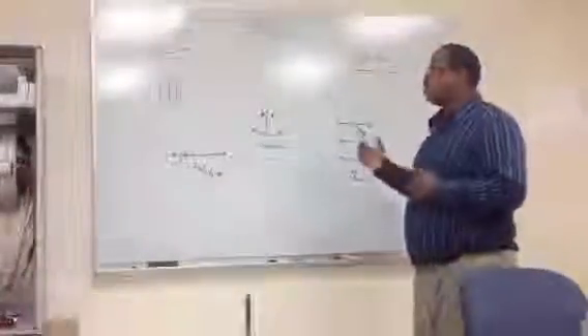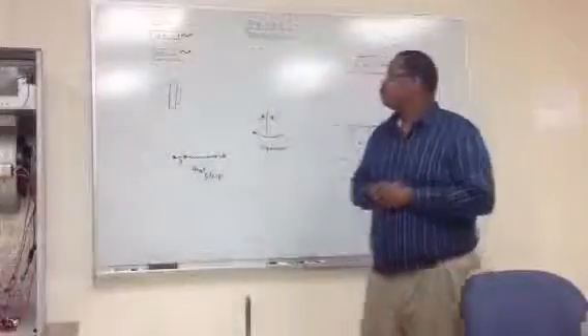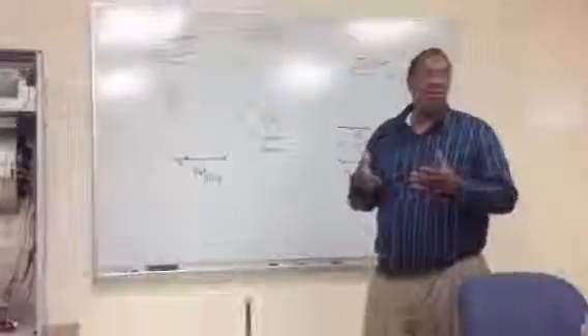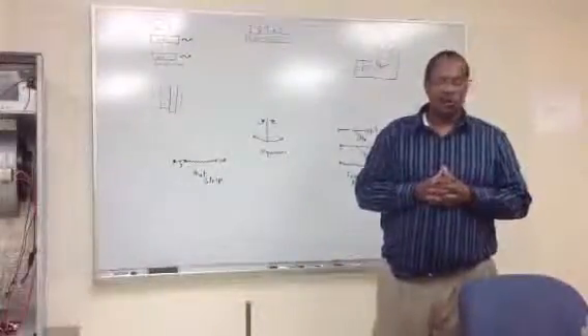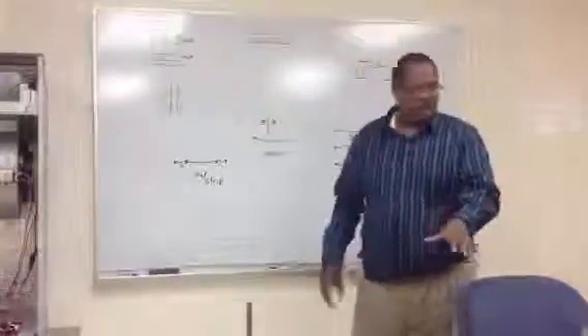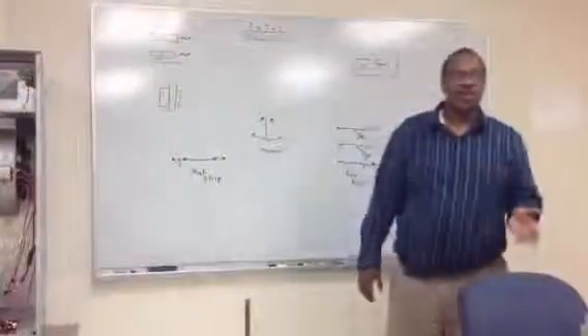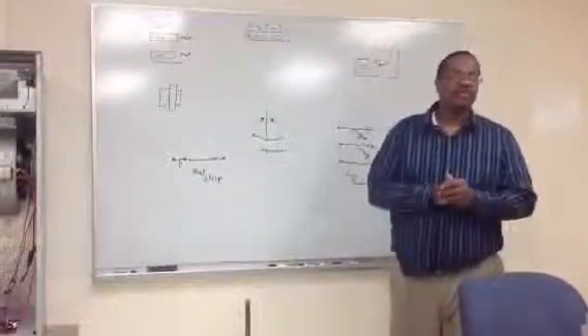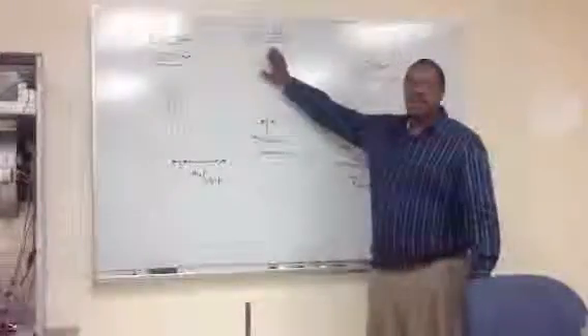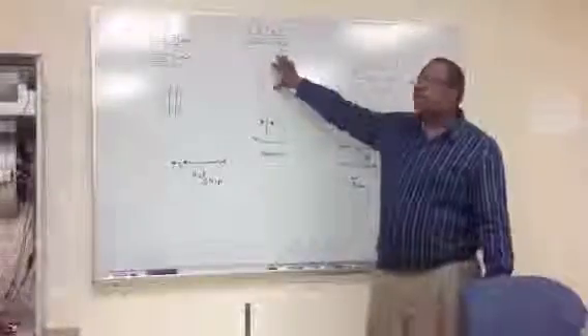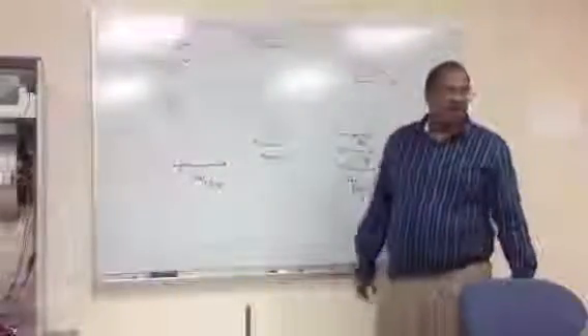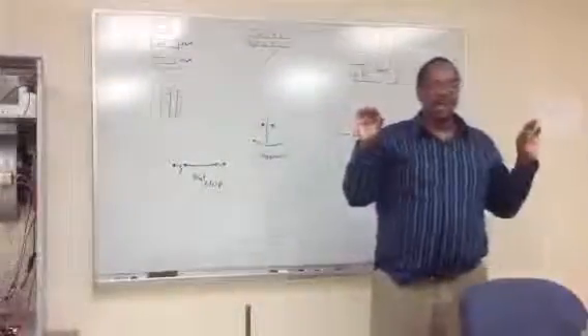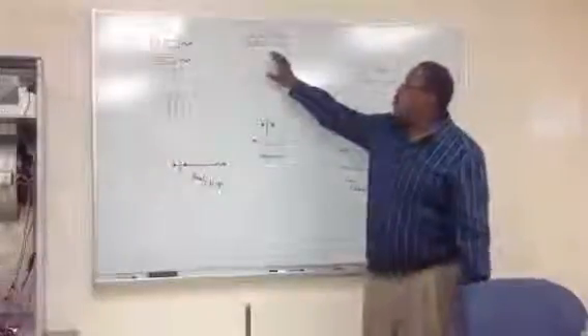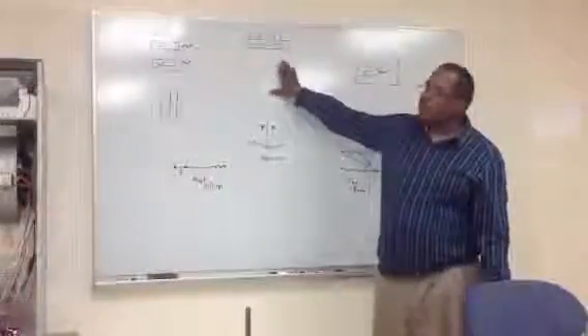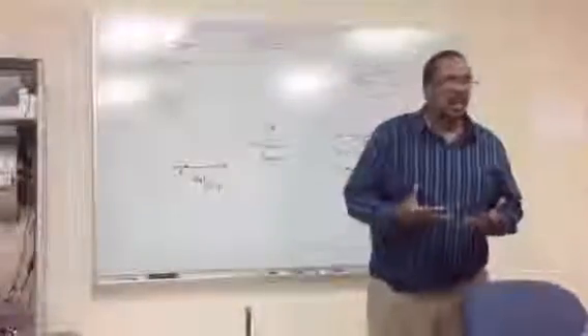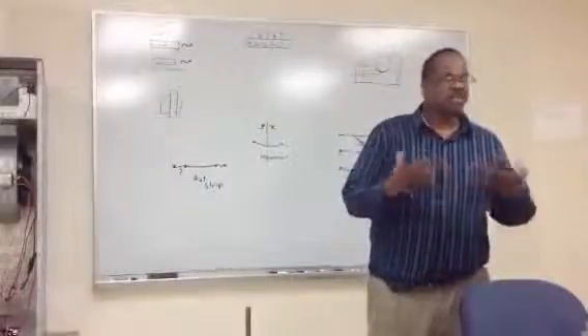Now, we're going to start off talking about the low voltage control before we start wiring up this unit. Well, what is the only switch in low voltage? It's the thermostat. Now, I don't have a thermostat here on the table, but many of y'all have seen thermostats. If you haven't seen a thermostat, then this video is not for you. This represents my thermostat in this drawing, where we will hook up the wires in the furnace that will go to the thermostat. Usually it'll be a little brown wire, a fine 20 gauge or 18 gauge wire. In later videos, when I show you how to wire up a furnace, you'll actually see those wires, where they're hooked up, and the thermostat itself.